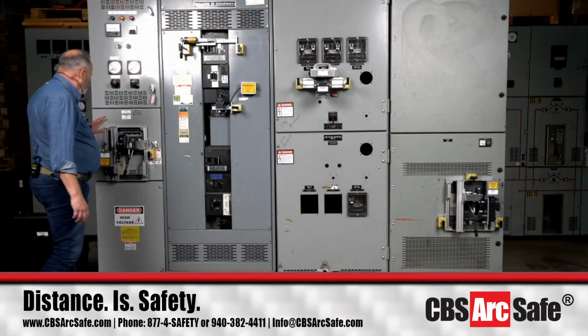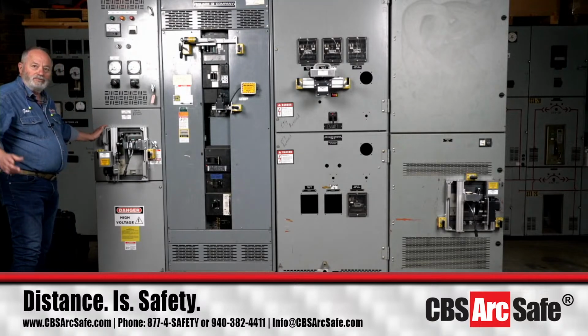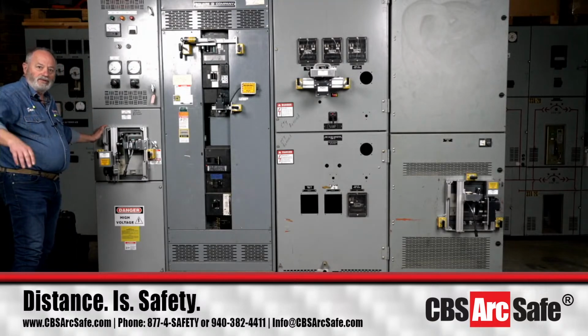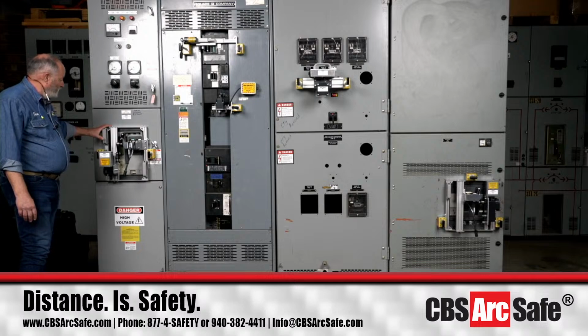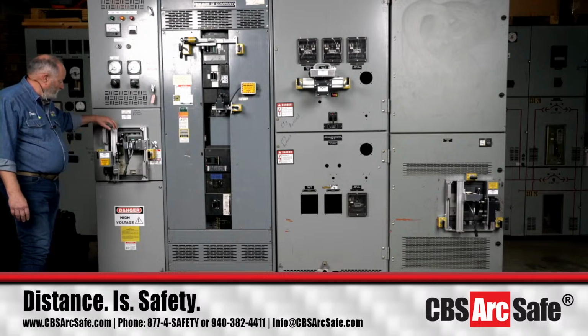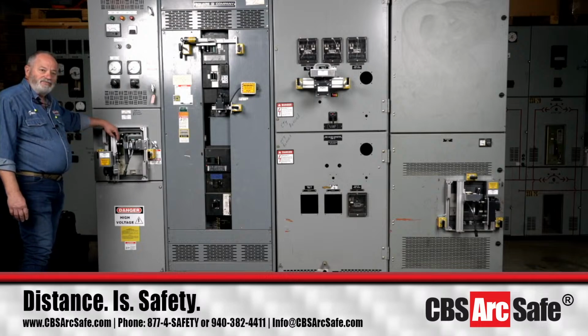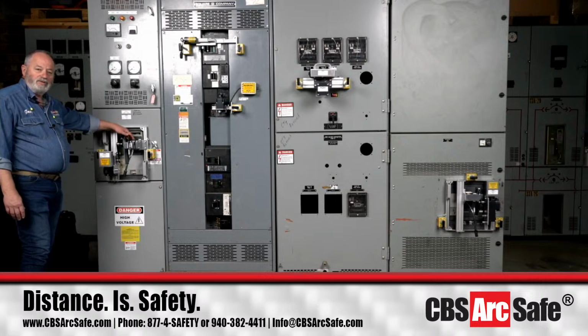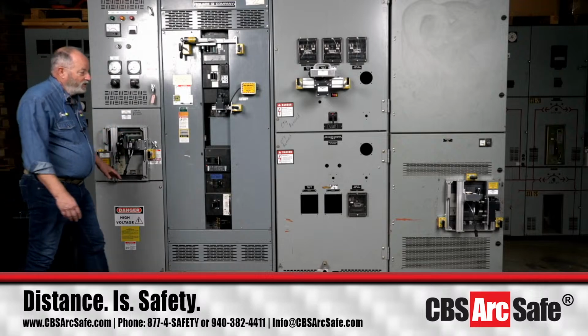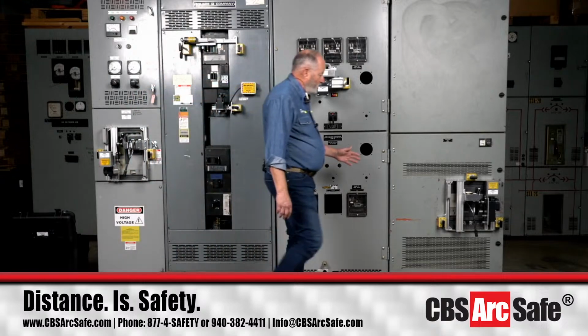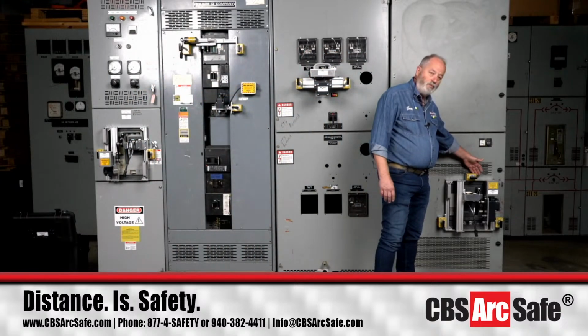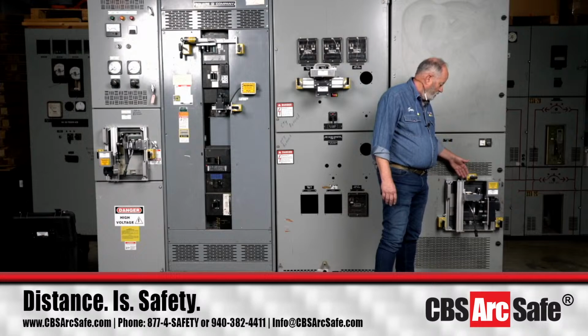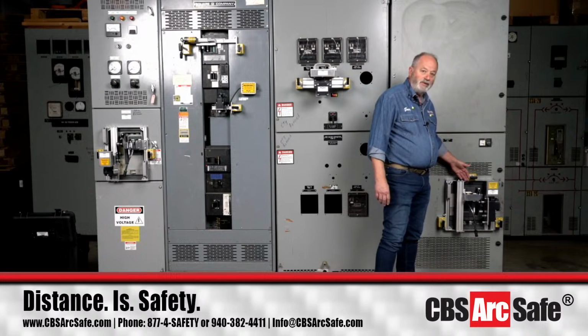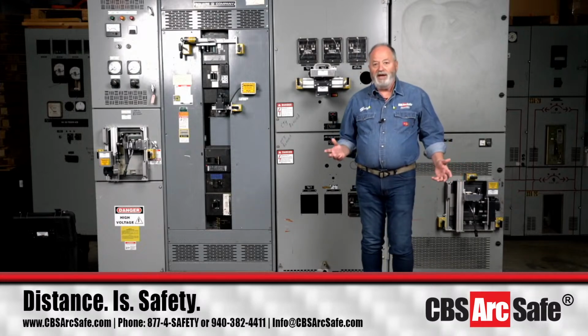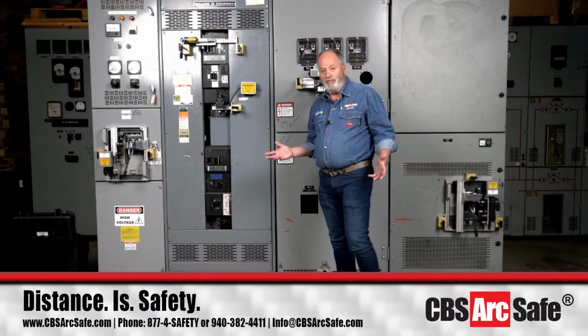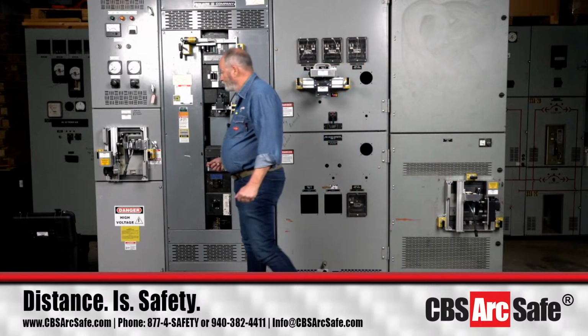Here is our racking system. You need to move the camera over this way to show the Magnum DS breaker. You'll see the charging handle is on the left side and the close/trip buttons are on the right side. If we look at our Masterpact over here, we've got our charging handle on the right side and our close/trip in the center of the breaker. So geometry drives the design of how we're able to do things to help you out.